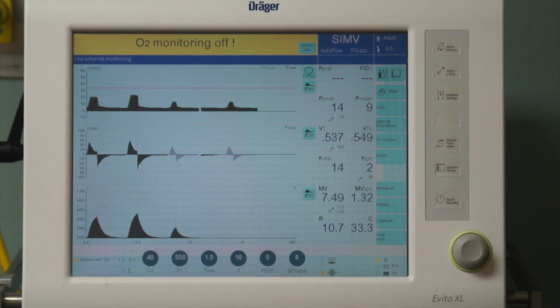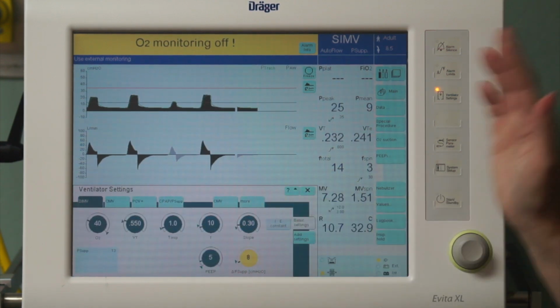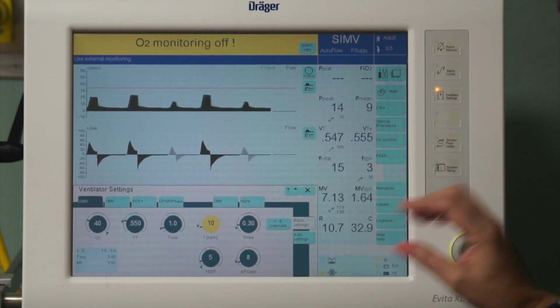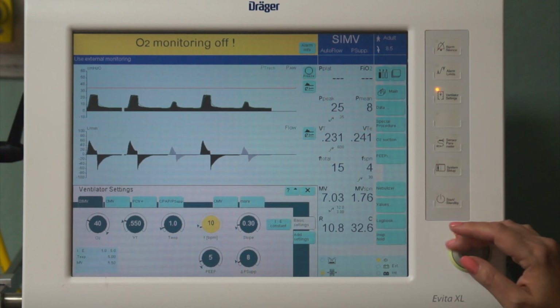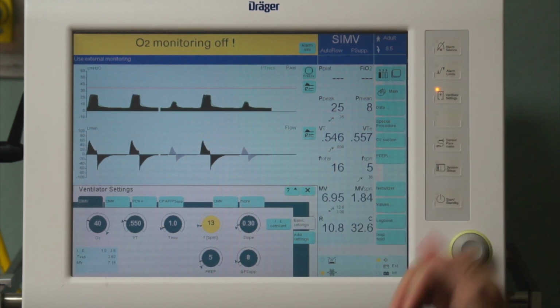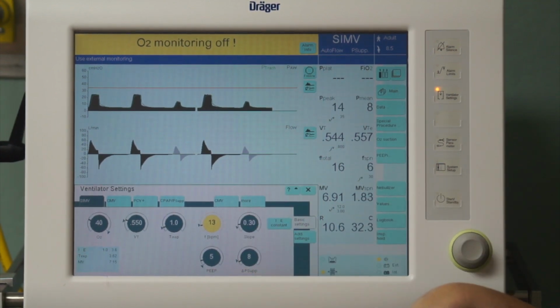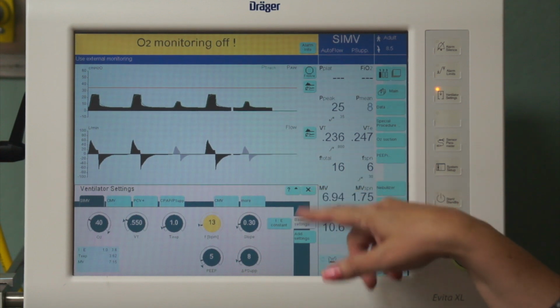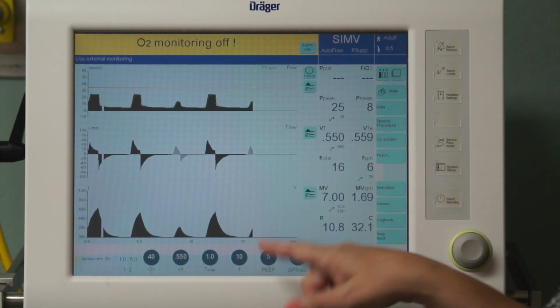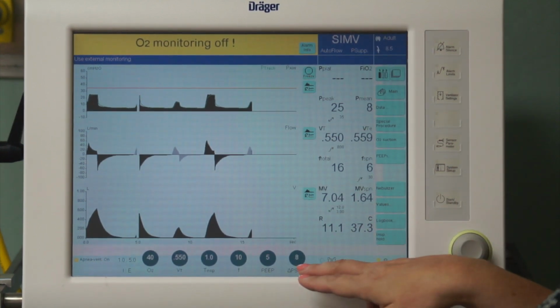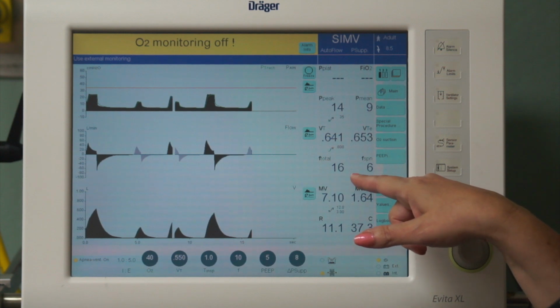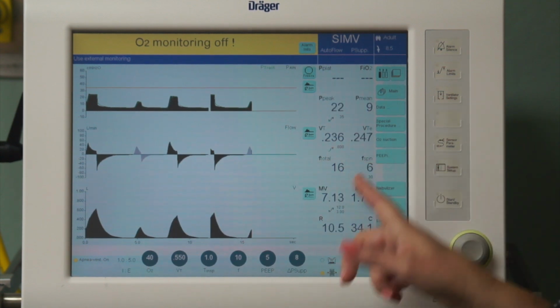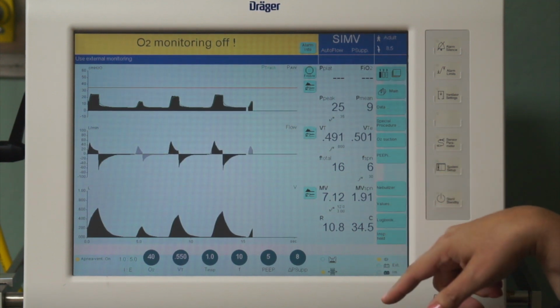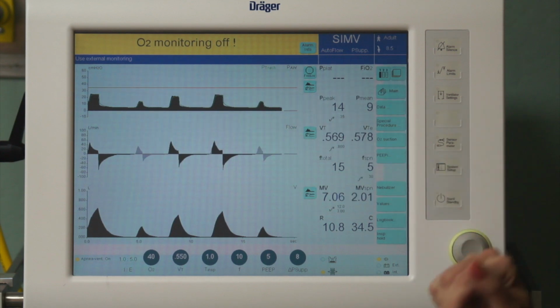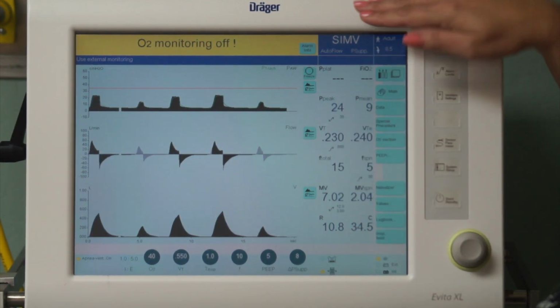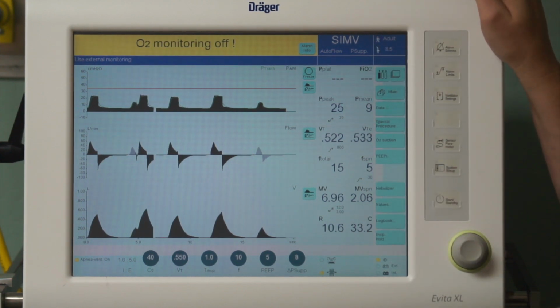So again, if I just want to change my pressure support, it's going to pop up. I get the whole system if I'm changing just the FiO2. But if I don't press this, nothing is going to happen. It's still not set. It goes right back to 10 because I did not press the button and make it change. Now notice what's happening. I have a respiratory rate of 16, and that's a spontaneous rate of 6. Okay, so I have 2 different kinds of breaths, and I'm getting all of this information right in here. You can read the majority of the things you want right in here.